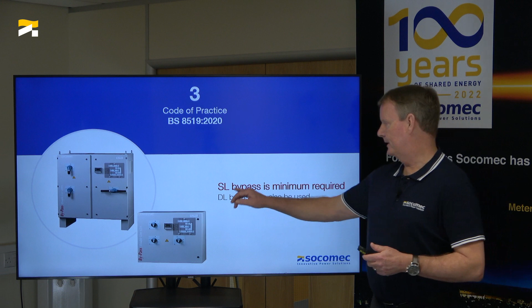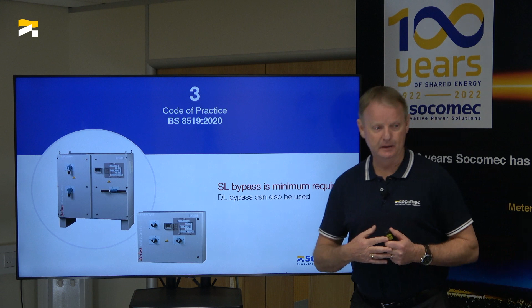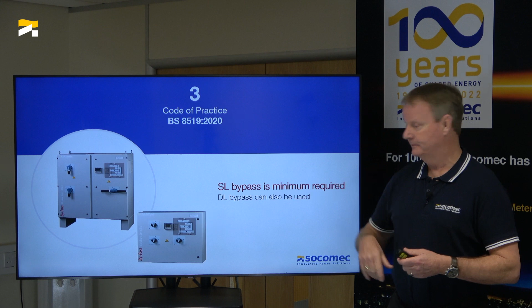Yes, correct. So the big difference is that if you're single line and you have the ATS out for maintenance, service, or checking, and you're actually going around the ATS, if you lose your primary source, you're pretty much stuck. You've either got to try to somehow get the ATS back into service quickly, but in my experience, if there's a fire and the ATS is out, whoever's in front of the panel is going to hightail it out of there as quick as they can.